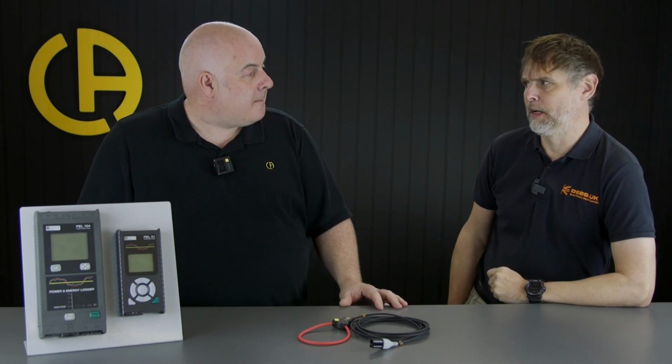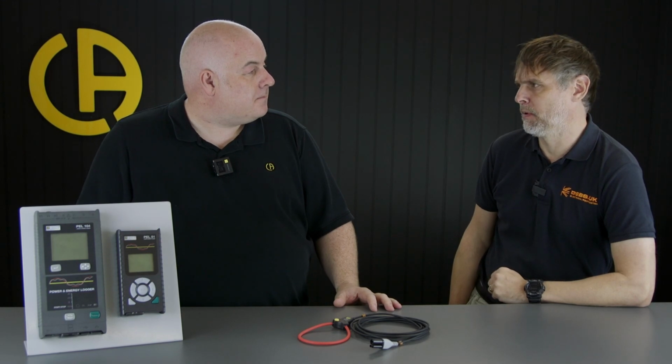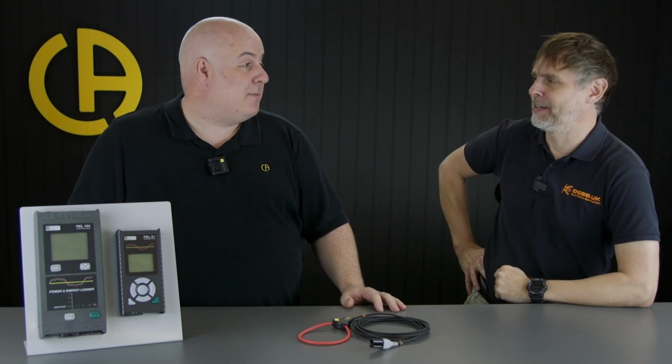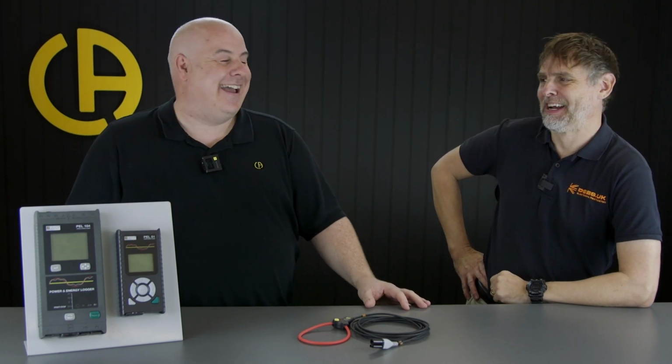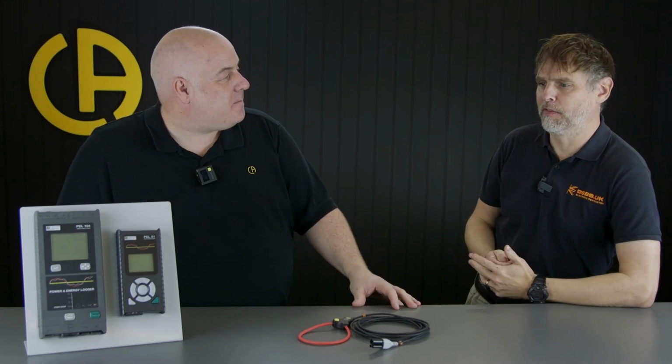Obviously when you've got an earth fault you can break out the IR tester and start taking some readings to try and narrow down where that's coming from, but overcurrent can be a little trickier to track down unless you've got an obvious smoking gun by something literally going bang. Smoke itself would be an interesting symptom, handy.